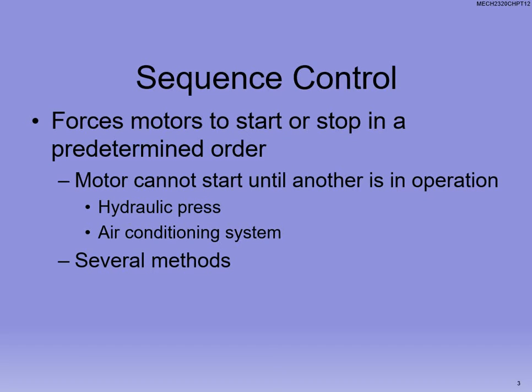So, sequence control — what's the whole purpose behind this? We want to be able to make motors start and stop, or start, or stop, or a combination of the two in a specific order. The first example is like a hydraulic press — you'd want the high pressure pump to turn on first before you could use the hydraulic press. And for an air conditioning system, you'd want the blower up and running before the compressor starts, since those are all on separate motors. The whole point is we want things to start and potentially shut down in a specific order.